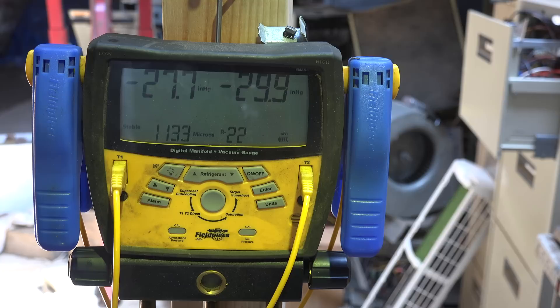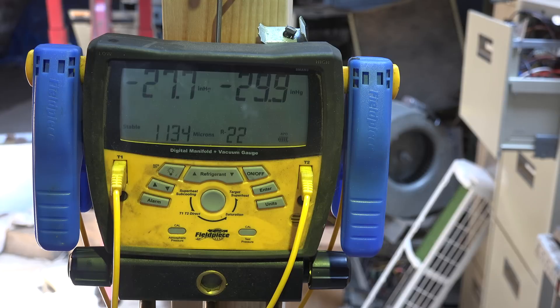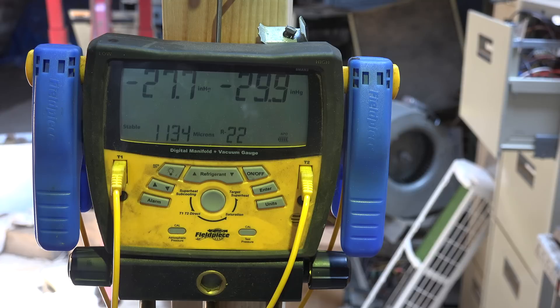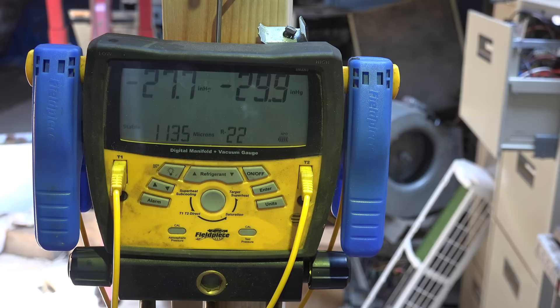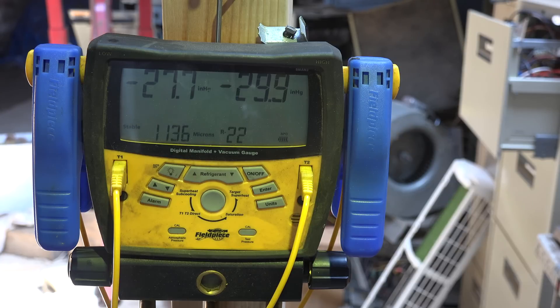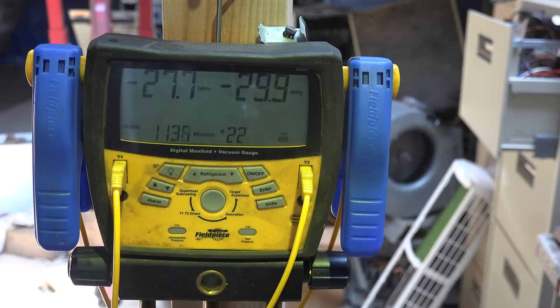It's an R22 system, so the oil is not hygroscopic, and it's not a real huge problem. Even if it was, it would be the same solution: a new, oversized liquid-line dryer. That will probably clean this up. That's all on this one.